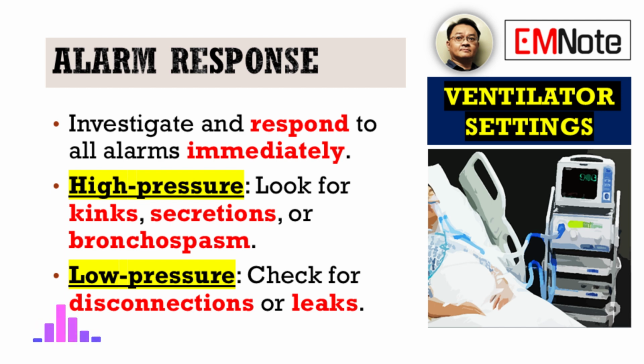And on the flip side, what about low-pressure alarms? What do those usually indicate, and what are the steps to resolve them quickly? Low-pressure alarms typically indicate a loss of volume or pressure being delivered. Air is escaping somewhere. The immediate action: check for disconnections anywhere in the breathing circuit. Start at the patient and work back to the machine. It could be a disconnection from the ventilator to the patient's tube, or a disconnection within the circuit itself. Hoses popped apart. Also, you must look for leaks, in the circuit tubing, or maybe around the endotracheal tube cuff. If the cuff isn't adequately inflated, air can escape around the tube. That's a common cause of a leak. A leak means the delivered volume isn't fully reaching the patient's lungs. It compromises ventilation. Both disconnections and leaks are serious. They compromise ventilation and require immediate, precise correction to get effective breathing reestablished fast.